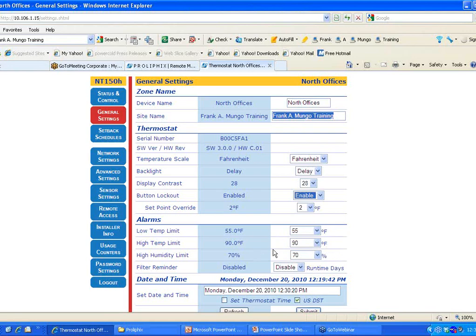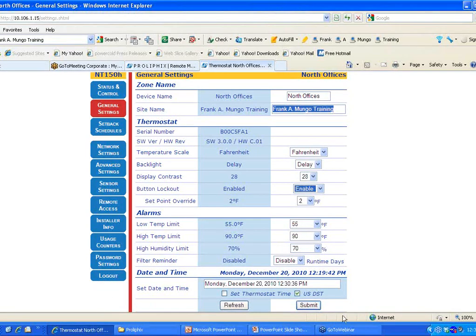You want to set these to be a little bit more, say 5 degrees more, than whatever your most relaxed set point schedule is. So your night setback schedule, if it's set for 60 degrees like ours is, we alarm at 55, because if it gets down to 55, that means something has failed. Then you can set the time and the filter and all that.